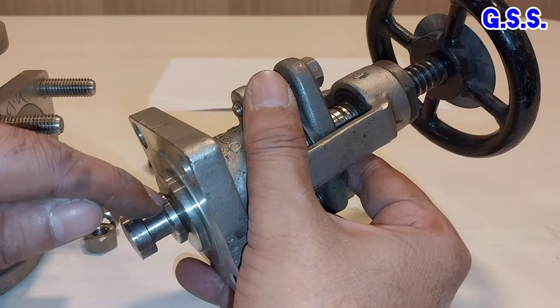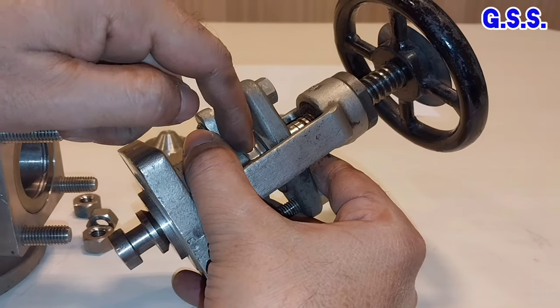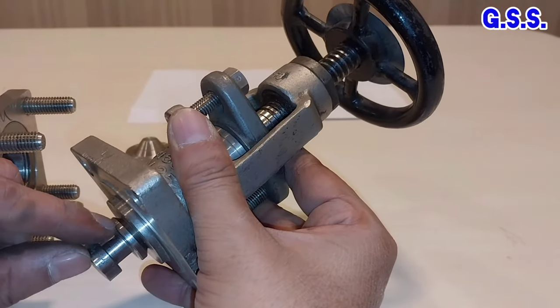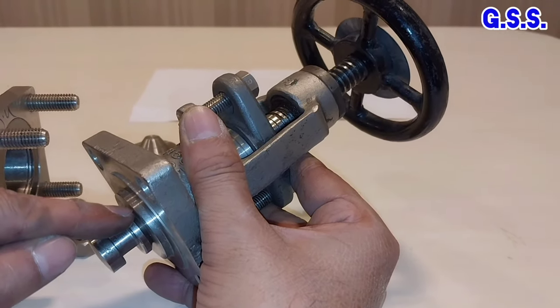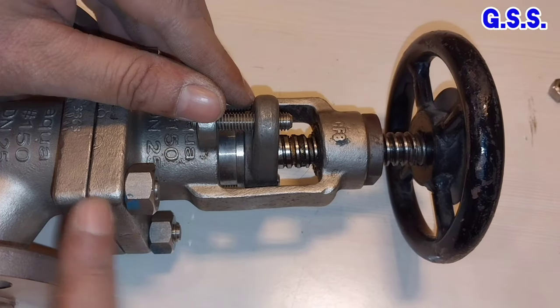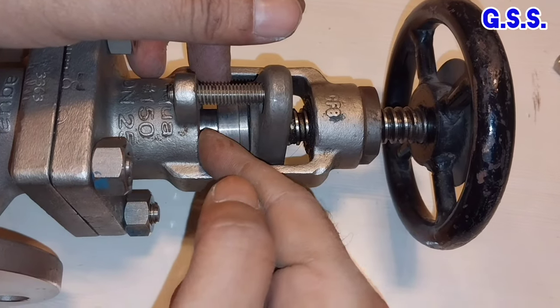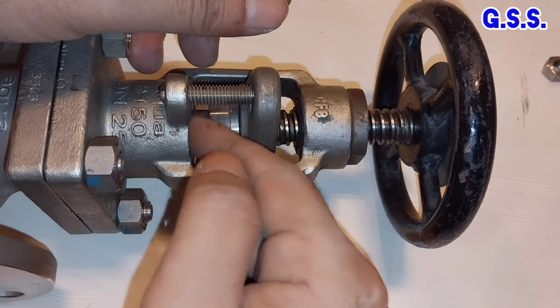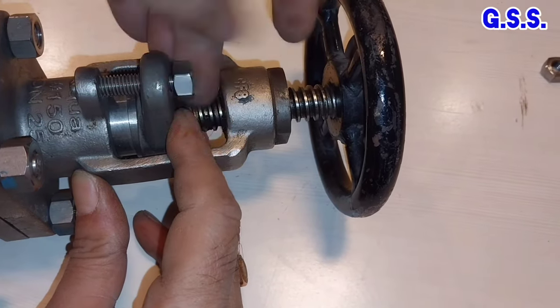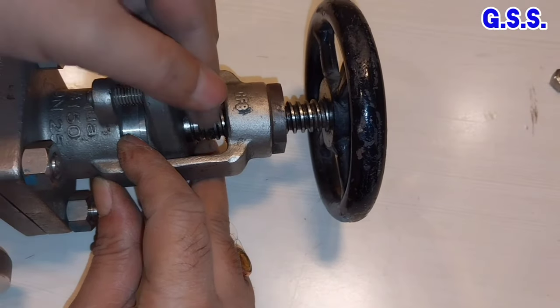Now it is fully closed to fluid passage. We can remove the gland flange and gland bush and replace the gland packing. For gland packing replacement, we have to make the valve fully open tightly so that the stem bottom will sit over the backseat tightly and there will be no leakage from here to the gland portion. For this type of ordinary gate and globe valve, we remove the gland flange first, then we remove the gland bush, and then we provide rope-type graphite packing here. Then we press the gland bush and then press and tighten the gland flange. The gland bush is tightened and new packing is installed.